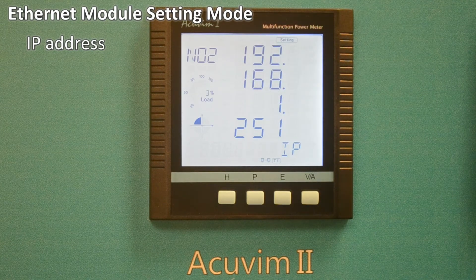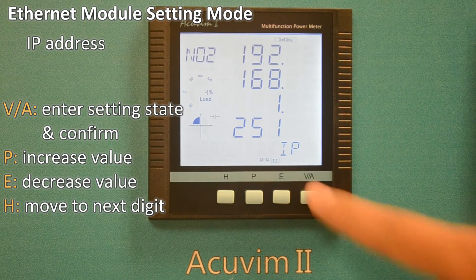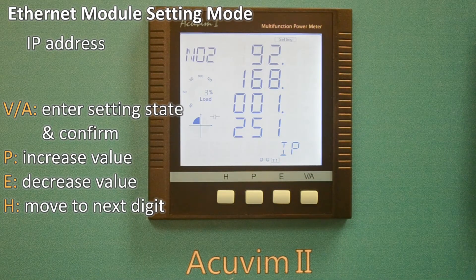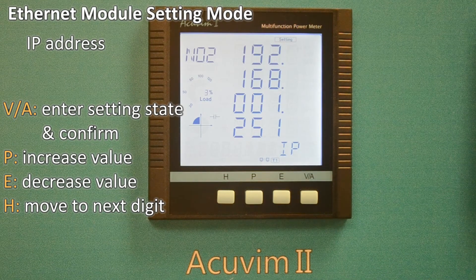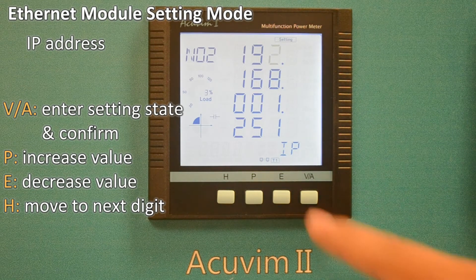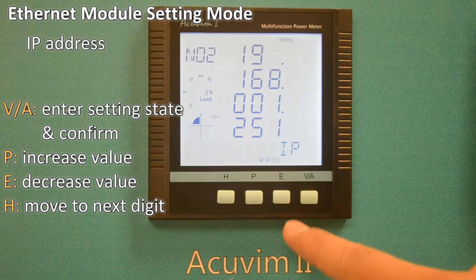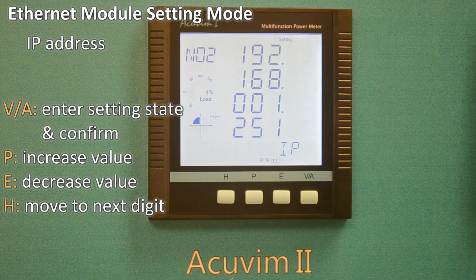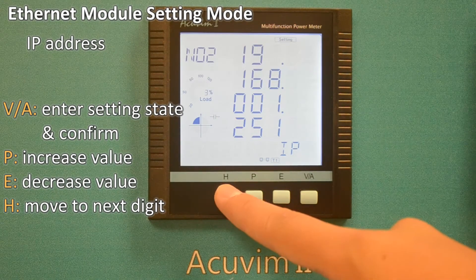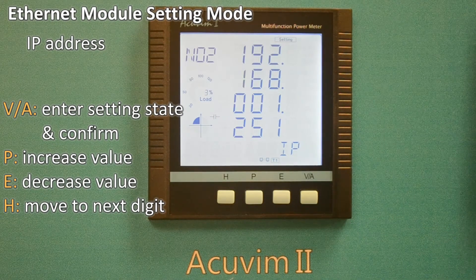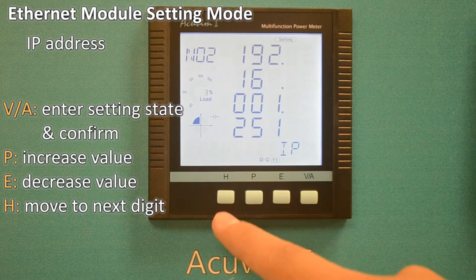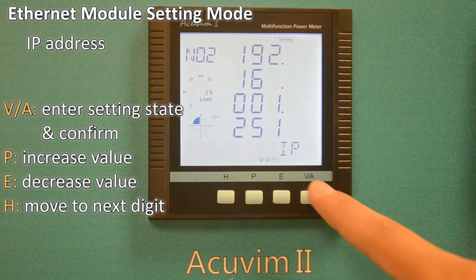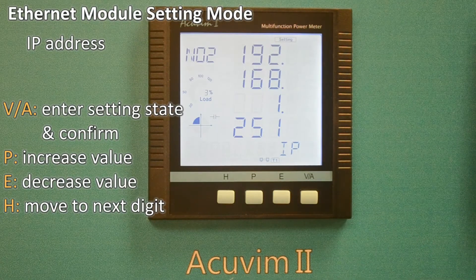To change the IP address, press VA to go to the setting state. The flashing digit indicates whether you are or are not in the setting state. You can press P or E to increase or decrease the value. After setting the first digit, press H to move to the next digit. Each digit of the IP address can be changed by this method. To confirm the IP address, press the VA key.